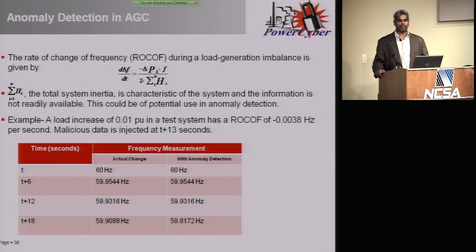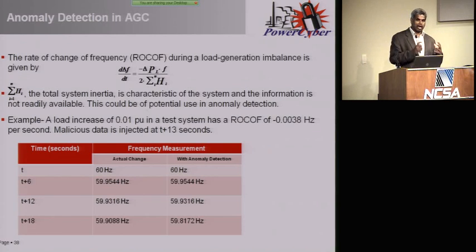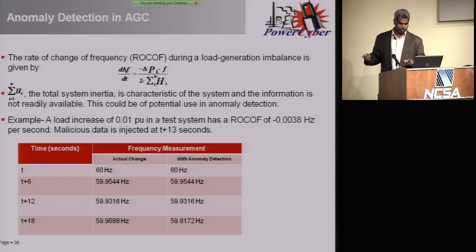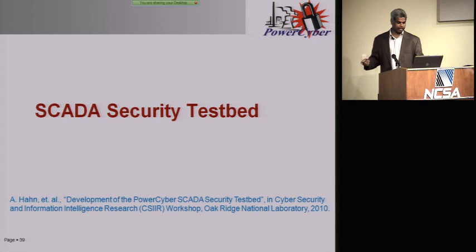That inertia information is not publicly available; only the power system operator, the system engineer, knows about it. That information can be plugged into an anomaly detection engine to flag when something is changing too rapidly, so those measurements get ignored until investigated, and the operator makes an intelligent decision. The point is there are mitigation measures to prevent this kind of attack.